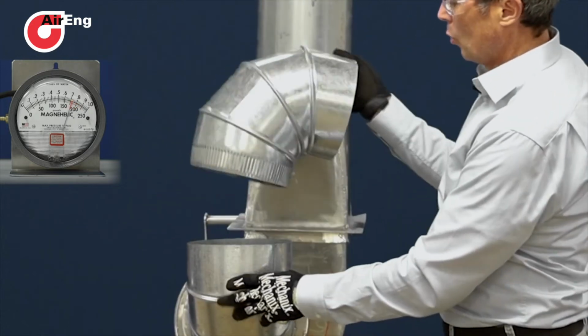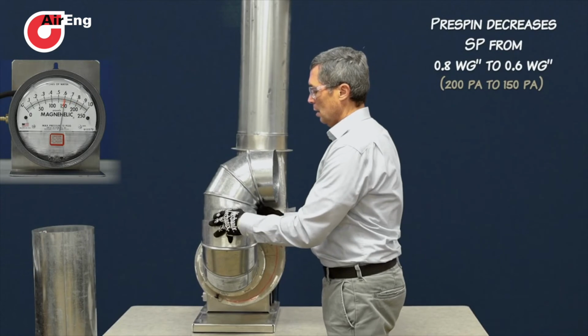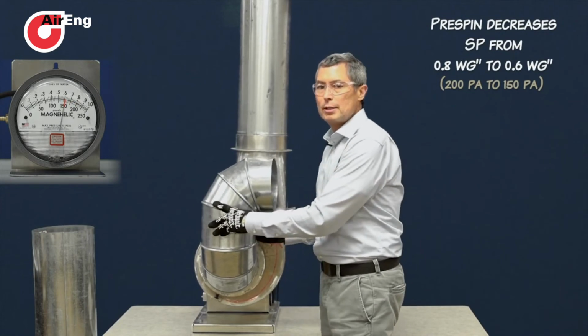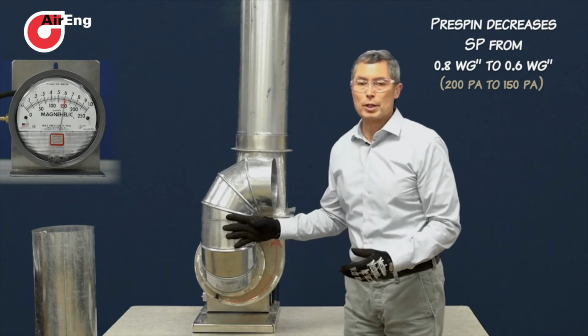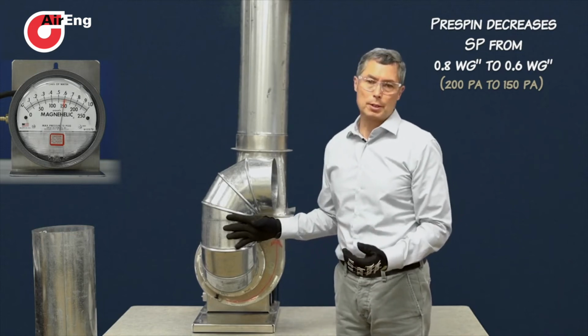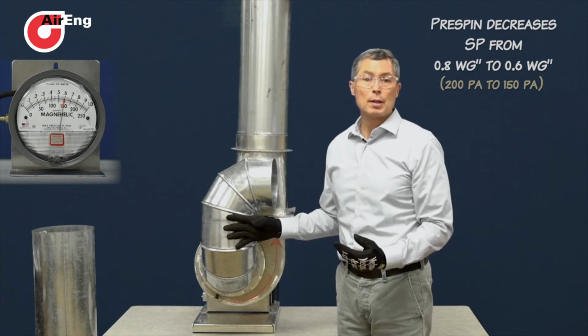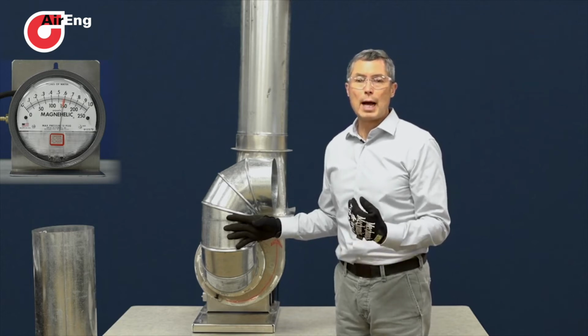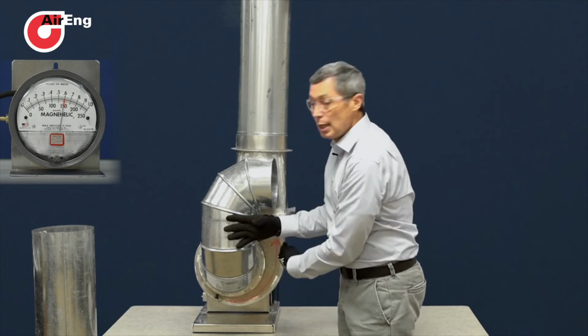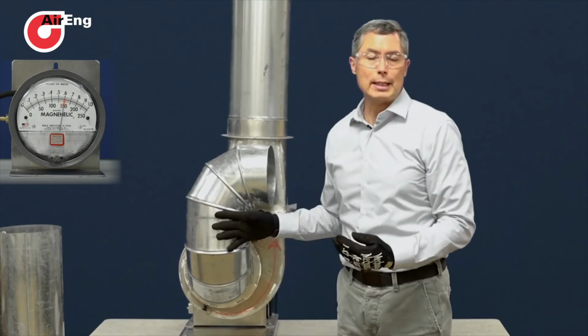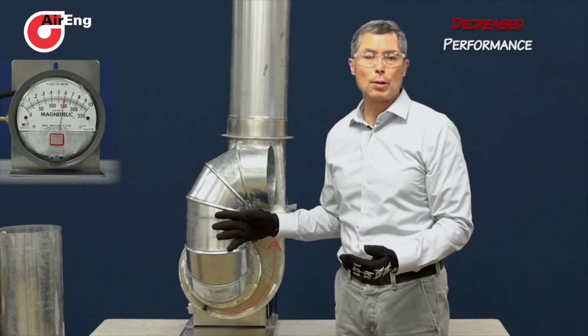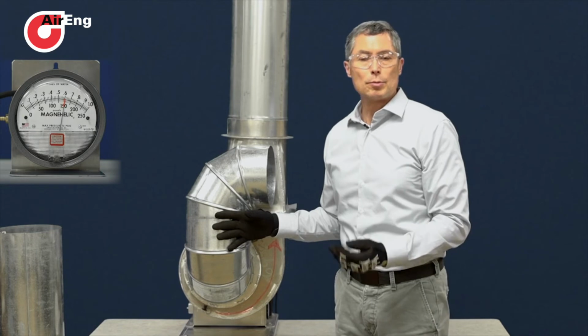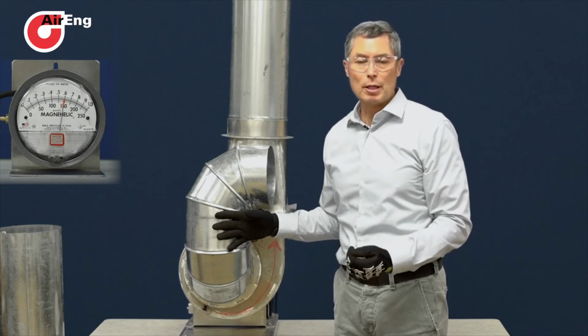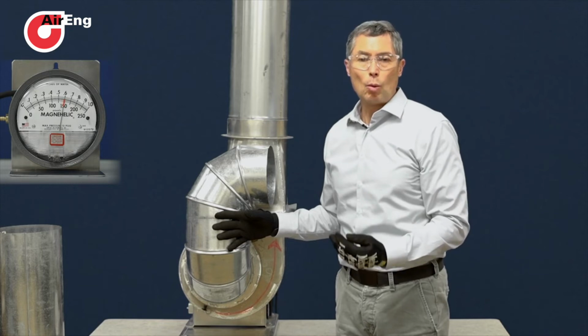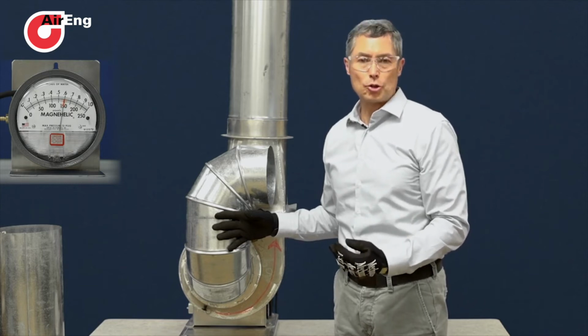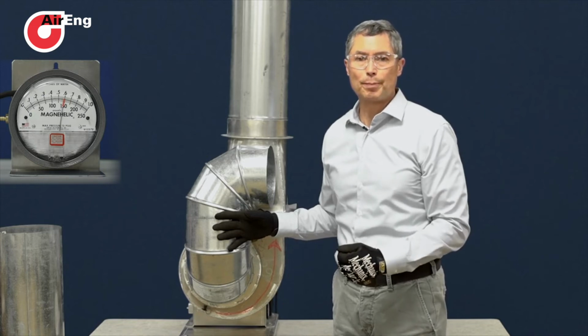We can rotate this 90 degrees. And now we are pre-spinning the air into the fan. And you'll notice a couple things. One is static pressure went down pretty substantially. Also, sound went down as well. And that's because we're now rotating the air in the same direction as the wheel is rotating, and that results in decreased performance. So that's similar to that same airplane taking off with a tailwind. The wing's ability to generate lift decreases pretty substantially. However, turbulent flow over that wing also decreases, resulting in lower sound levels.